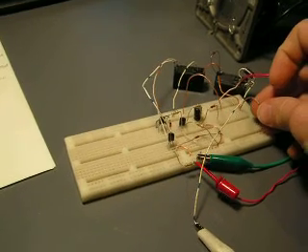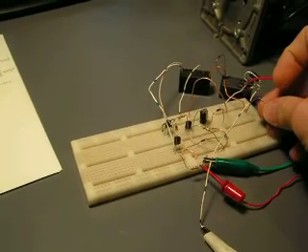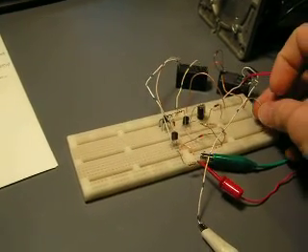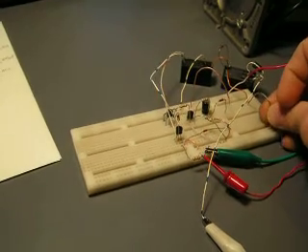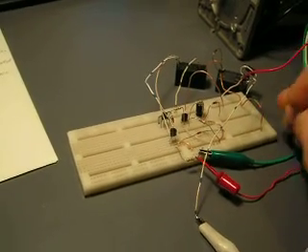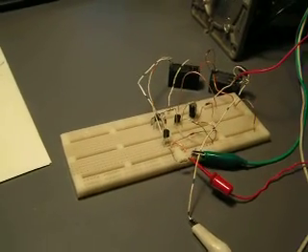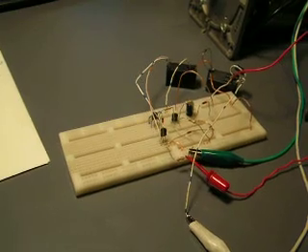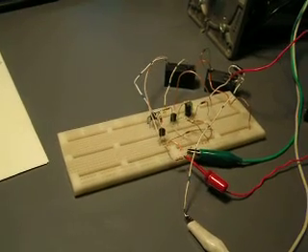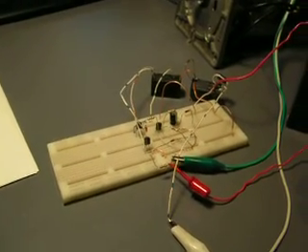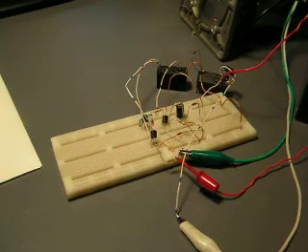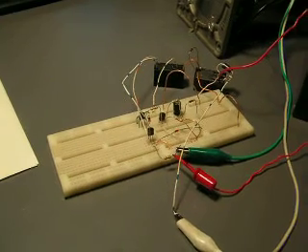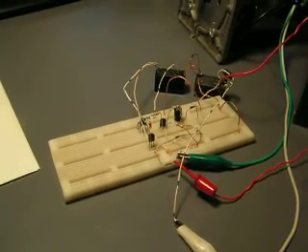Okay. This is enabled. And I'm just disabled there. It stays enabled for the enable time, which is set at ten seconds. After which time, even if something were to happen, say for example an end-of-travel switch failed, the system would no longer try to push the windows up. It's sort of a safety, a fail-safe.